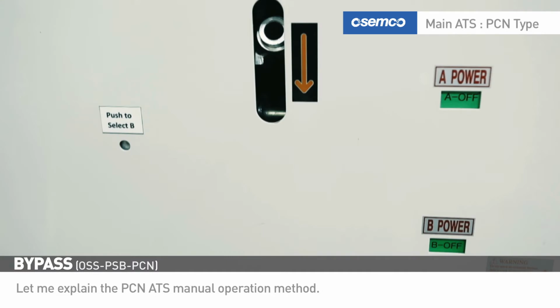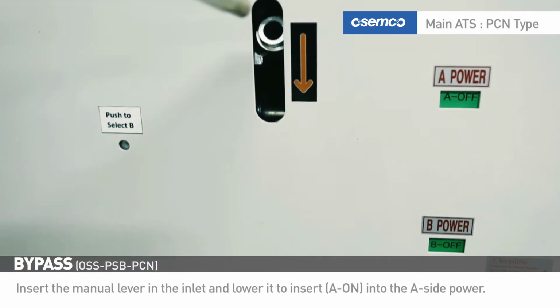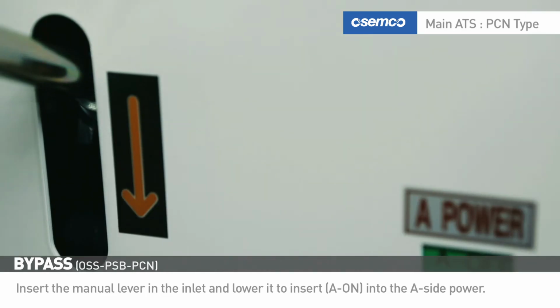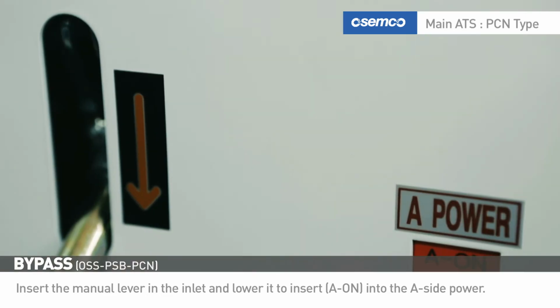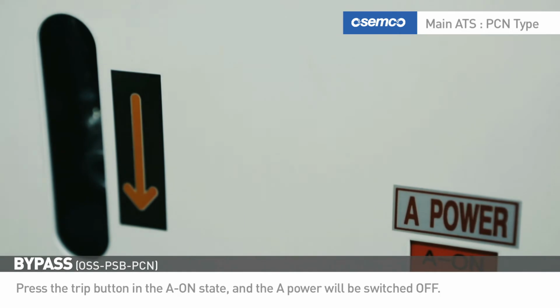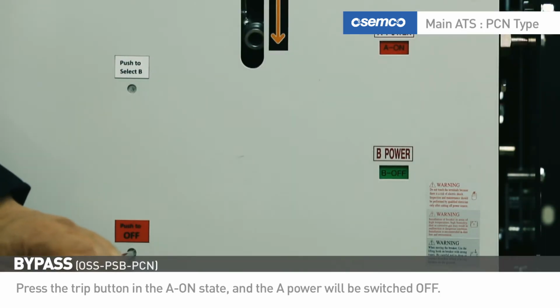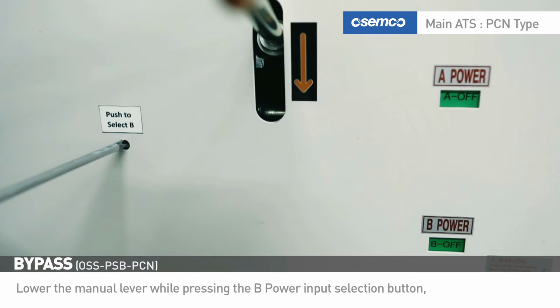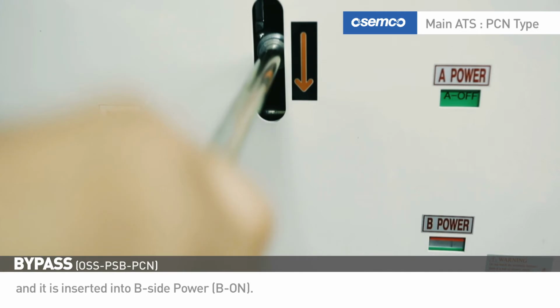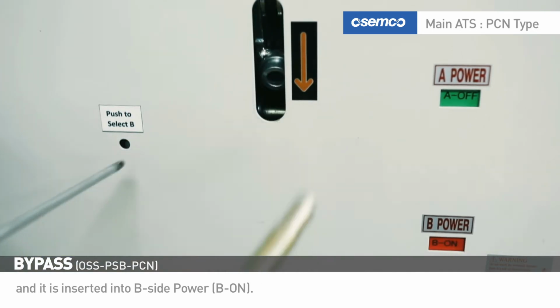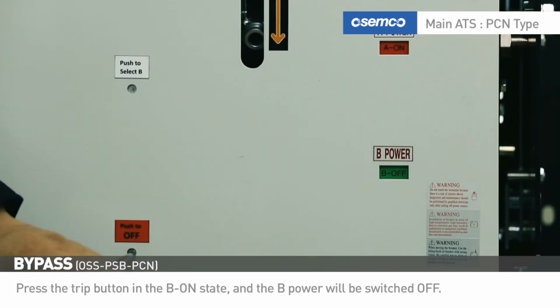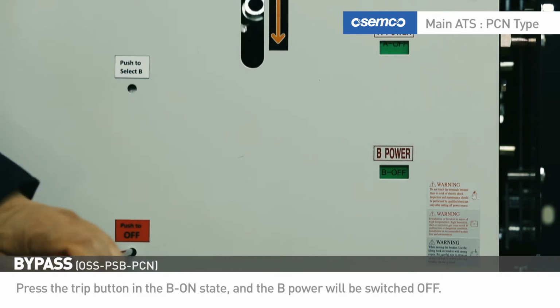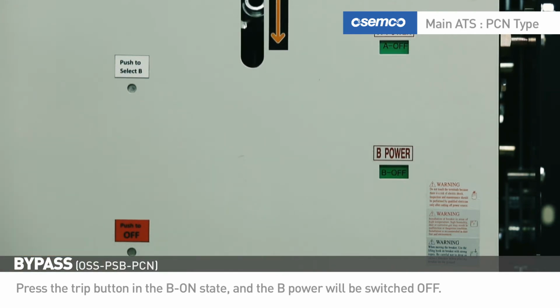Let me explain the PCN ATS manual operation method. Insert the manual lever in the inlet and lower it to insert A on into the A side power. Press the trip button in the A on state and the A power will be switched off. Lower the manual lever while pressing the B power input selection button, and it is inserted into B side power, B on. Press the trip button in the B on state and the B power will be switched off.